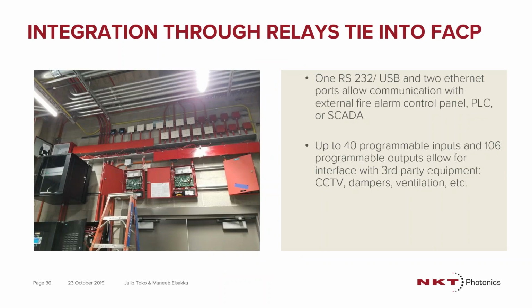Another thing that you can do is the integration to fire panel. This is really one of the easiest things to do because we are designed exactly as any other detector system. The controller itself is compatible to most fire panels. So there is no requirement about which fire panel we are compatible to, and that is the case for any other fiber optic linear heat detection vendor. They are all compatible to most of them.